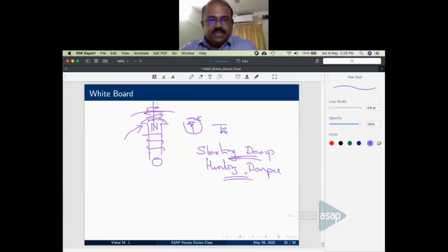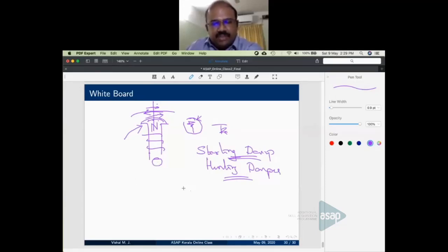And do you mean to say measure the rotor speed and adjust the PWM starting delay between 0 and 90 degrees for controlling the phase? Yes, that is exactly what is being done. You sense the speed, you extract the frequency component from that, and use that as the frequency to the stator. For example, consider a 50 hertz machine. 230 volt is the phase voltage. Now the rotor is rotating at some speed, correspondingly 20 hertz.